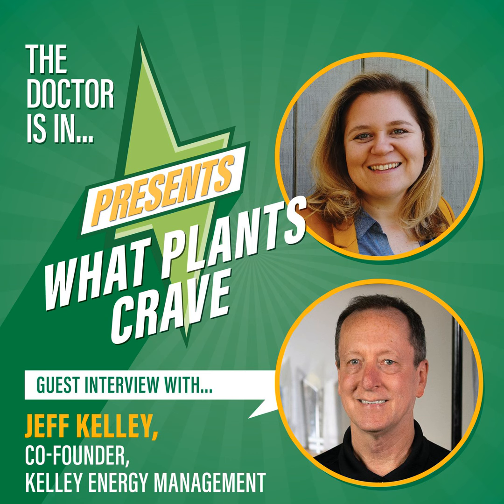Right. Do you talk to the manufacturers about the sequence of operations, at least at a high level, of their equipment? So if they had a digital scroll plus a two-stage compressor, do you talk to them about which is the lead compressor, which is the lag compressor, how they work together, and when you would expect one to switch over to the other? We'll look at it that way, and then we'll look at the program and ask whether the program is going to pick up that particular thing. Then it becomes like, what's the kW per ton at the set point, at that point in the cycle of the unit? So you're doing an abstract thing to model that.